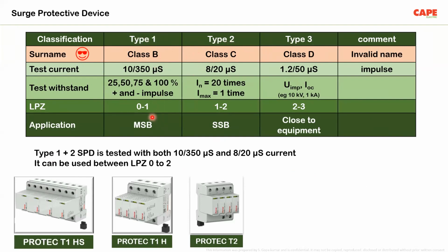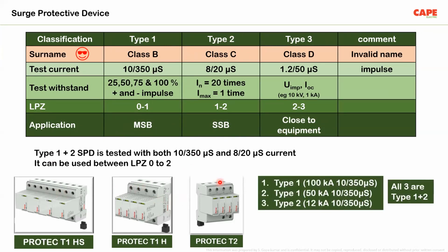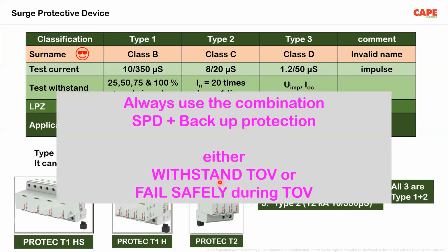Where do we use a type 1 SPD? At the main switchboard. Type 2 at the sub switchboard. Type 3 closer to the equipment. So these are the devices, the culprit which created the explosion as per that particular video. Of course, there are several categorizations of SPDs. I won't go into it much. What you should select or understand is, always use the combination of SPD plus backup protection. Either this combination is able to withstand the TOV or fail safely during a TOV. If this test is not mentioned in the catalog, or if this test is not carried out by the manufacturer, please don't use these SPDs. It will actually create its own problem.